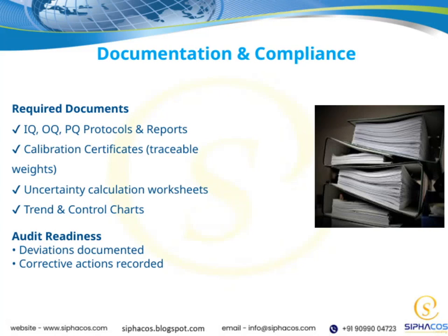Let's talk about documentation and compliance. First, there are the required documents we need to have in place, such as IQ, OQ, and PQ protocols and reports. These are essential for showing that our equipment is installed, operated, and performing as intended. Next, we need calibration certificates, especially for traceable weights, to ensure our measurements are accurate. It's also important to have uncertainty calculation worksheets. They help us understand the level of confidence in our measurements. And finally, trend and control charts are vital tools for monitoring our processes over time and identifying any deviations early on.